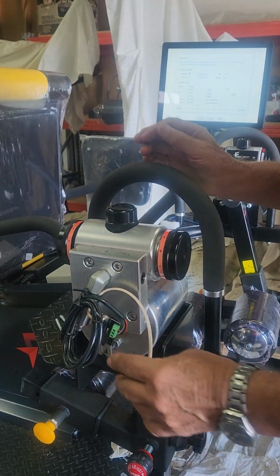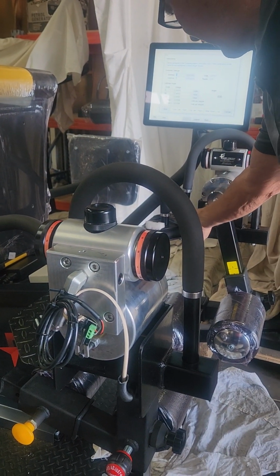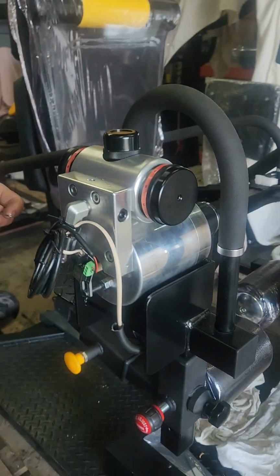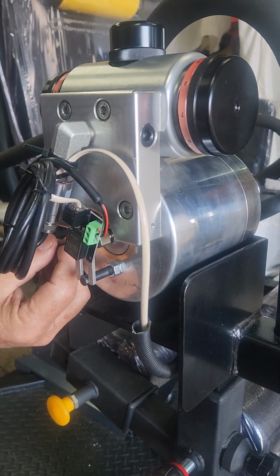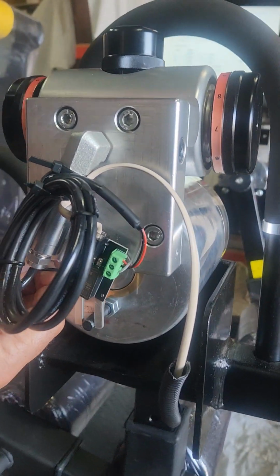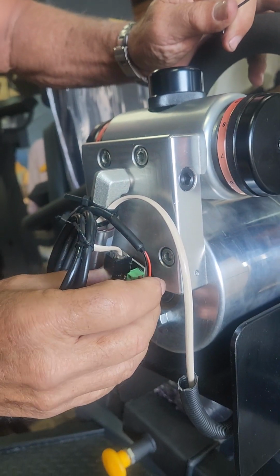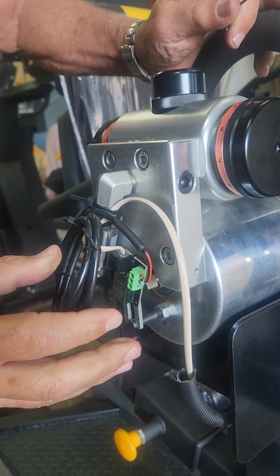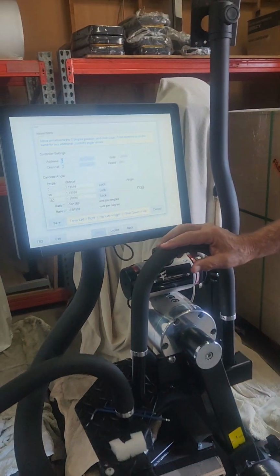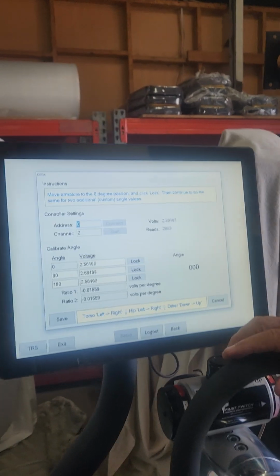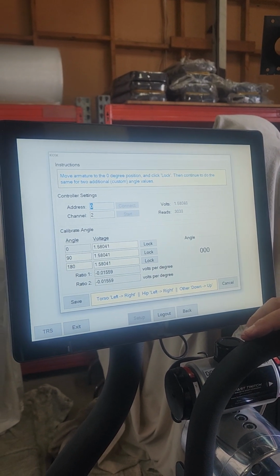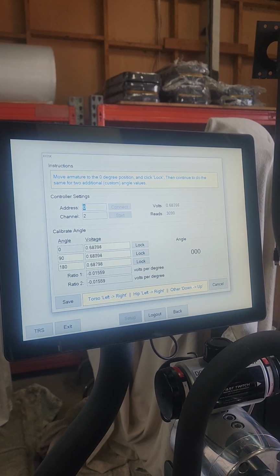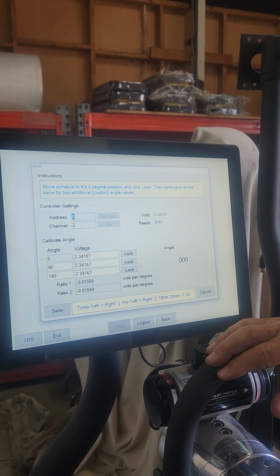the drive, you'll just need to lock the little grub screw that's locking the angle sensor, just right here. So you get an Allen key, and I just lock that in, which means I've just locked the drive bolt of the motor to the angle sensor there. So it's all locked in position, and then I can test on here when I'm moving that arm up and down that it's staying within the 5-volt range. Because it's impossible to lift your leg up that far, that's well within the 5-volt range.